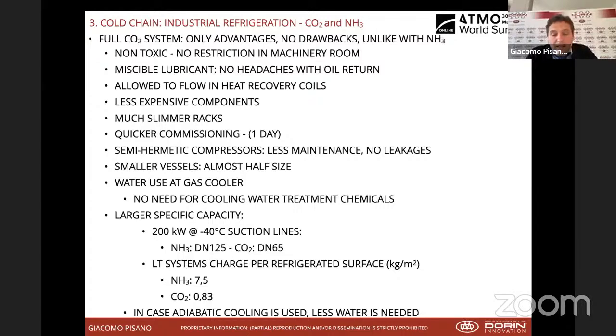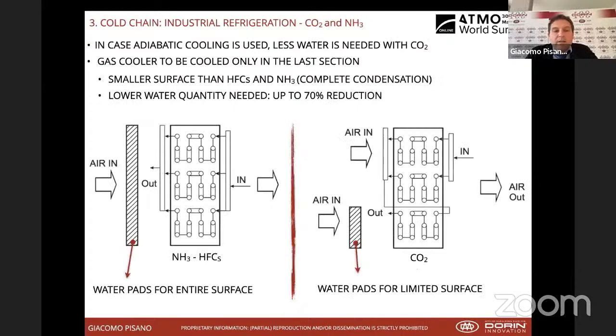0.83. In case adiabatic cooling is needed, you can also think about using less water with CO2. This is basically due to the fact that for CO2, you are working in transcritical operation. And this means that the surface of the gas cooler has to be wet at a lower ratio. When working with ammonia or other HFC refrigerant, you can do adiabatic cooling, but you need to wet the entire surface of the condenser, while with CO2, in principle you can only apply water pads, and in theory only at the very last section of the gas cooler, because you need to provide some subcooling and you do not have condensation throughout the entire flow pattern of the gas cooler itself.